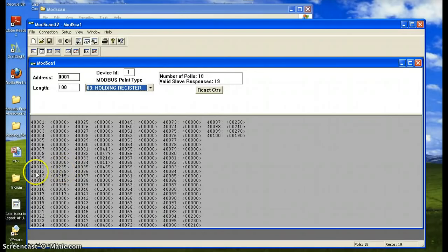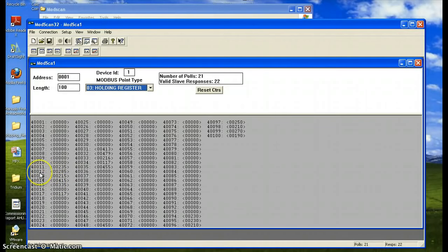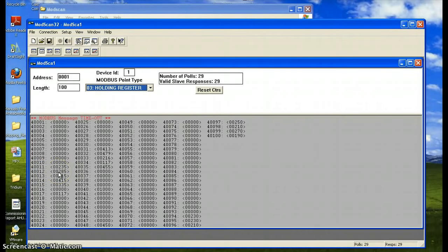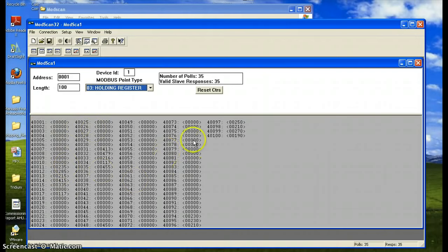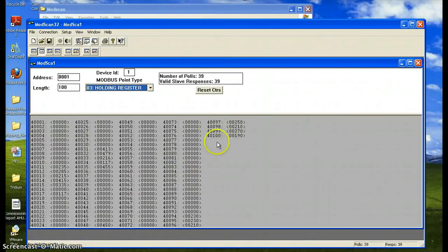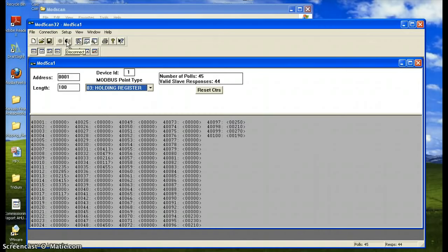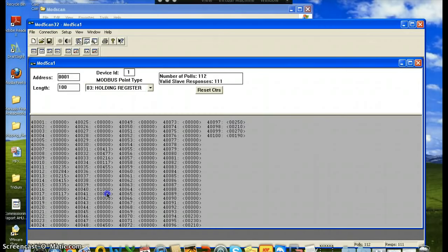In this specific application, the target software is an air handling unit where Modbus address number 12 as a holding register is my supply temperature at 28.5 degrees. Through this I can scan through my network and easily see the correct reference of my Modbus list to the software.